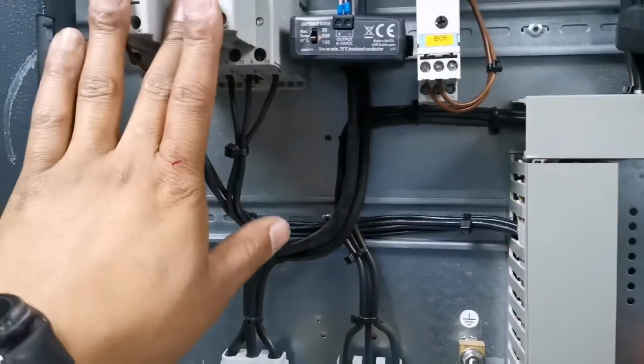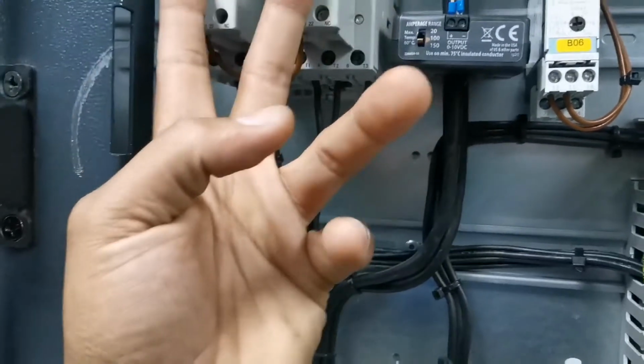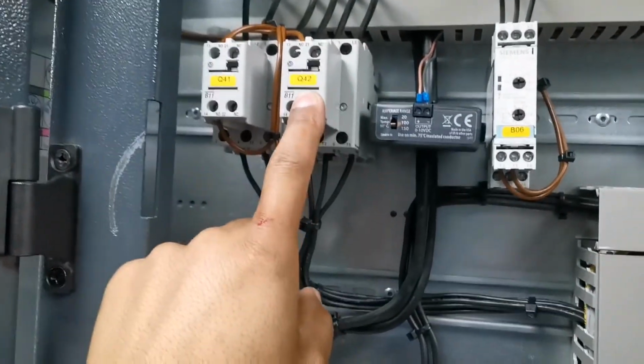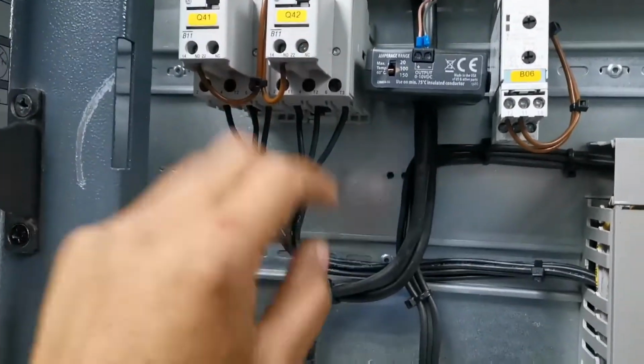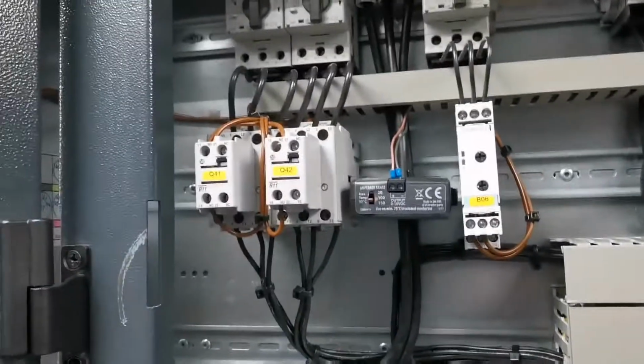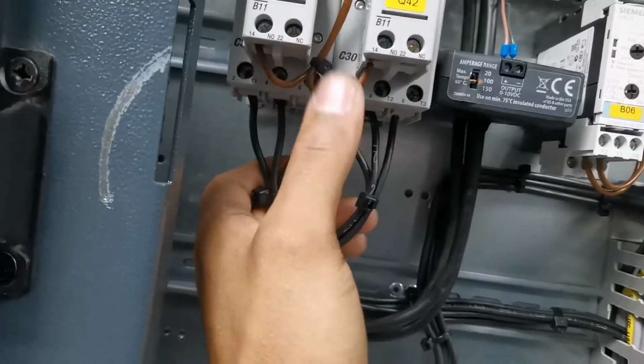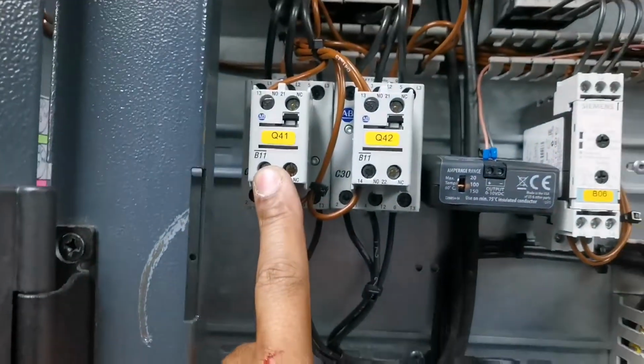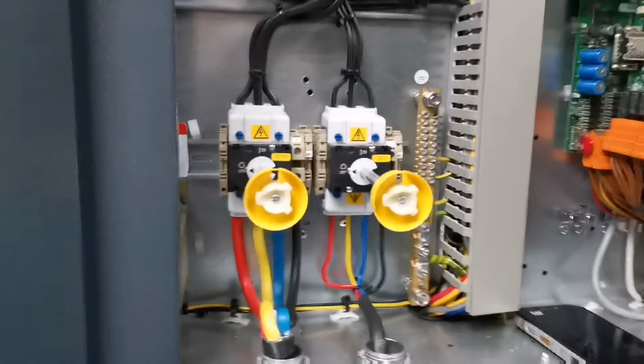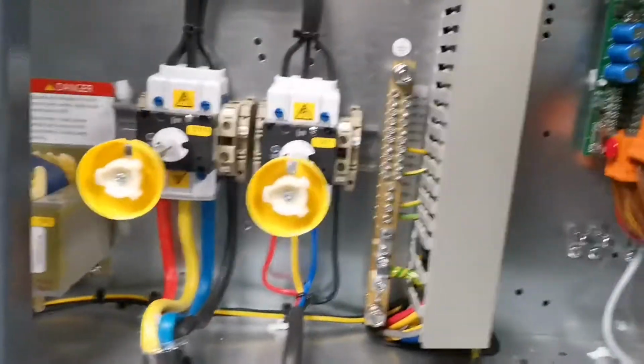So what tech support suggested is that we swap the 2 contactors and see if we now get a HP2 alarm on circuit 2, which will then let us know that intermittently our contactor is actually the cause. So I'm gonna go ahead and swap these, and then I'll let you guys know if that solves the issue. Alright guys, so everything's swapped around. The only thing that I haven't changed was the supply. The load is changed around, and all the controls that come into the normally open on the contactor. So let's switch power back onto our unit, and we'll have a look and see.